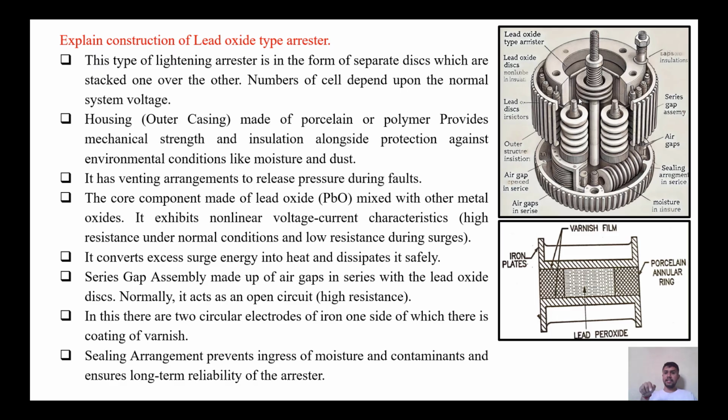Housing, that is casing made up of polymer or porcelain material, provides mechanical strength and insulation alongside protection against environmental conditions like moisture and dust. It has venting arrangements to release pressure during these faults.